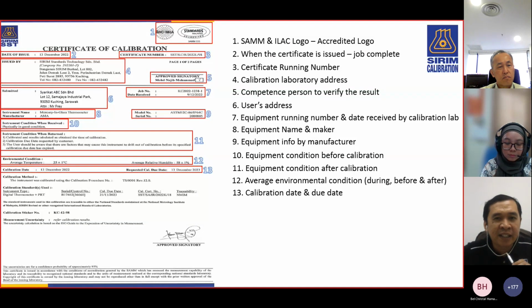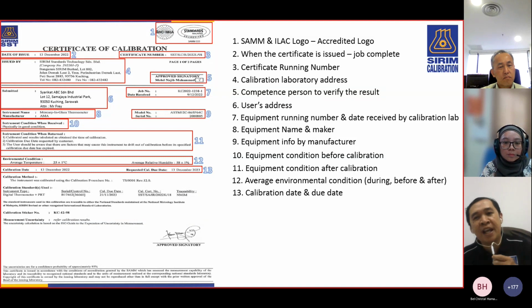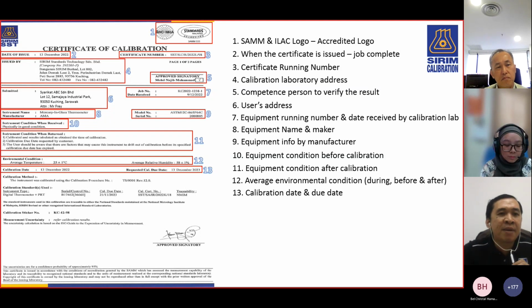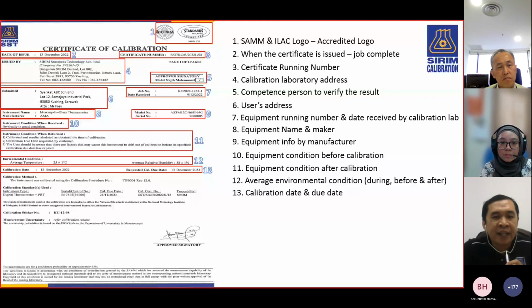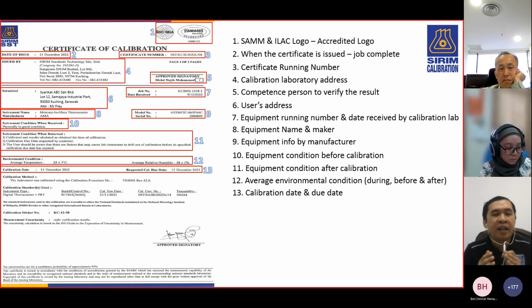Okay, this is a very important one: calibration date and due date. As you can see here, the requested calibration due date is 1 year starting from its calibration. Usually we put this due date if the customer requests 1 year. For those who request more than 1 year, we leave the calibration due date blank, because we do not know how frequently the user uses the equipment. The more you use your equipment, the more frequently you need to send it for calibration.